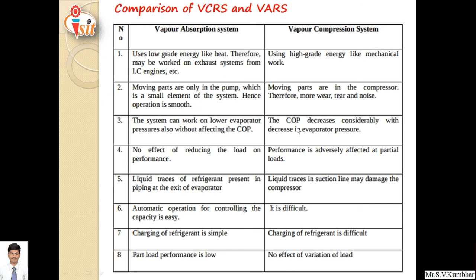Third difference is COP: in vapor compression, coefficient of performance decreases considerably with decrease in evaporator pressure; vapor absorption can work at lower evaporator pressure without affecting COP. Fourth: performance is adversely affected on partial load in vapor compression; vapor absorption shows no effect of reducing the load on performance. Fifth: liquid traces in suction line may damage the compressor in vapor compression — if liquid from the evaporator accumulates in the suction line it may choke and damage the compressor; in vapor absorption there is no compressor, so it does not cause any problem to the generator or absorber.